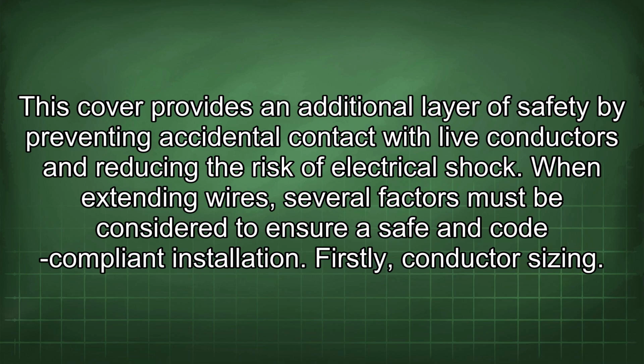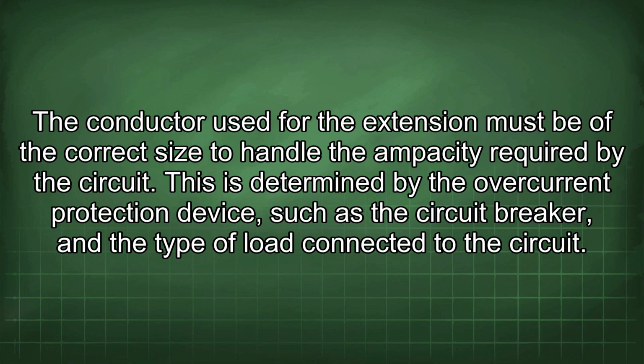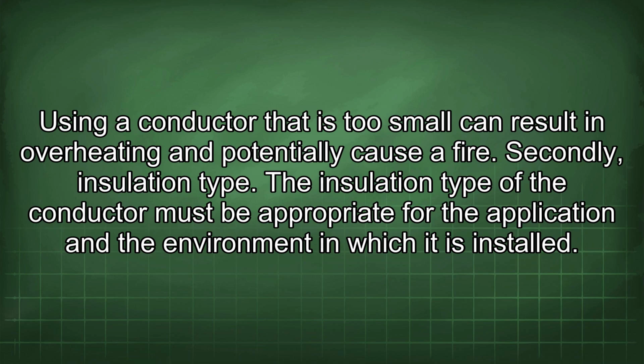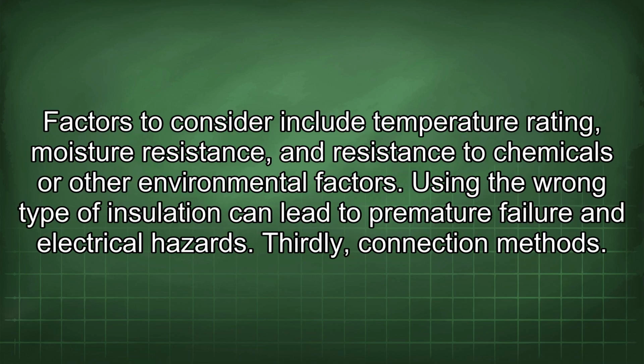Firstly, conductor sizing. The conductor used for the extension must be of the correct size to handle the ampacity required by the circuit. This is determined by the overcurrent protection device, such as the circuit breaker, and the type of load connected to the circuit. Using a conductor that is too small can result in overheating and potentially cause a fire. Secondly, insulation type. The insulation type of the conductor must be appropriate for the application and the environment in which it is installed. Factors to consider include temperature rating, moisture resistance, and resistance to chemicals or other environmental factors. Using the wrong type of insulation can lead to premature failure and electrical hazards.